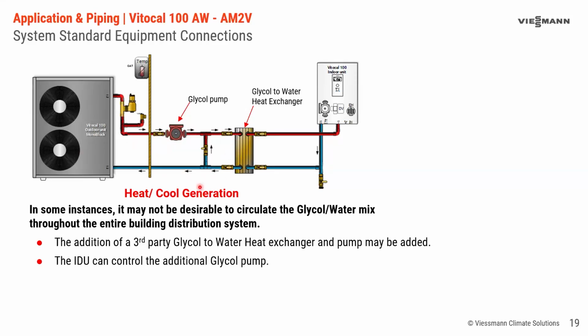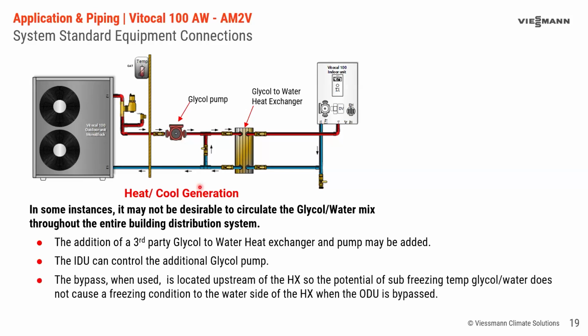Now, in a lot of cases, we're going to put a bypass in here. So if we're going to put a bypass in here, we want the bypass on the glycol side of the heat exchanger, not on the water side of the heat exchanger. And here's the reason why we want to do that. If we had this bypass on this side, and we were using the indoor pump, and we were supplying water and bypassing and going back to here, and this pump here was still moving glycol water to the heat exchanger, we could get into a position where this side would be below zero glycol water.